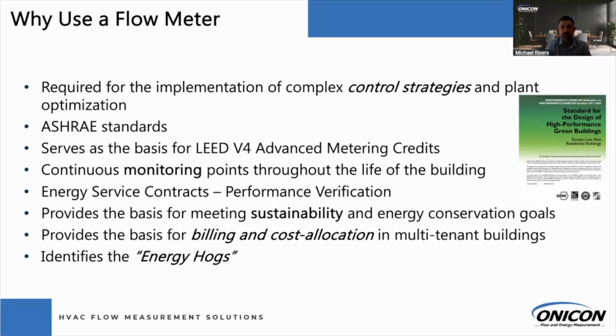And then lastly, billing. It's not quite fair to bill off of square footage. You're seeing more and more tenants starting to bill off of BTUs. And then the last one here, those are my three main points. The last one that I've really seen more recently is sustainability, or having our end users wanting to measure their ESG initiatives, where typically you only get one bill from the utility of how much water consumption or gas consumption. Well, if you have more flow measurement throughout your system, you can understand where the water is being consumed and start meeting those conservation goals.